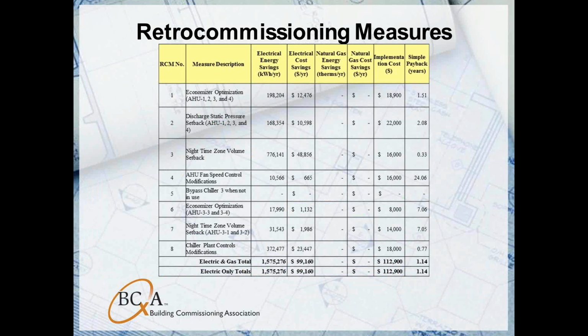So these are the measures that we came up with in our initial pass. These are our energy savings measures as part of the retro commissioning project. Our target for this project was 800,000 kilowatt hours. Step 1 is RCM 8 here: we want to reprogram our chiller plant so that we can attempt to solve our operational issues first. That's the first and foremost thing that we wanted to do.